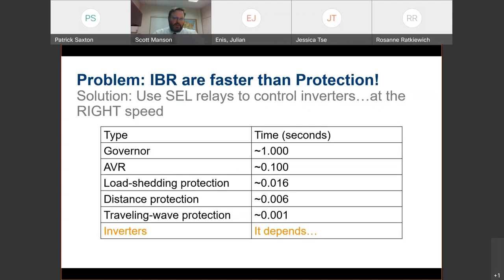Doesn't work. So how do we universalize inverters so that they can adapt and integrate together on a basis in a microgrid and the macrogrid everywhere? Well, what you do is you have inverters become very simple. You take the intelligence out of the inverters, and you make them act homogeneously the same everywhere, reducing your overall cost, because let me tell you, inverters are a lot more expensive than protection devices. And you control them with relays. And you dictate the speed at which they move with a protective relay. That relay then controls the time frame at which this power system changes. Now you've solved the problem. Again, it has to do with distributed intelligence. Things that work too fast, you can't see and you can't operate, so you slow it down.